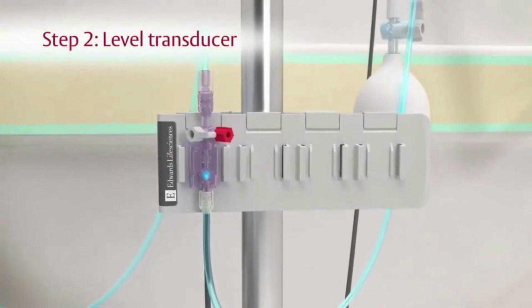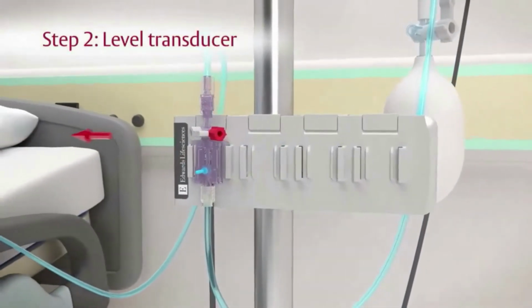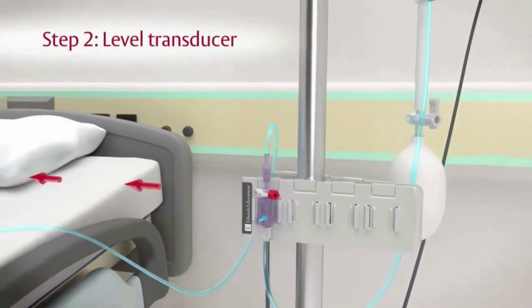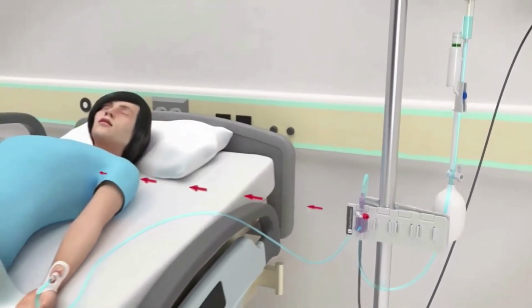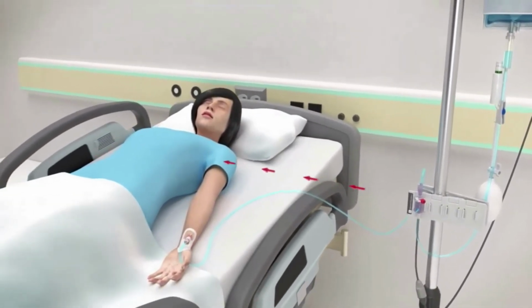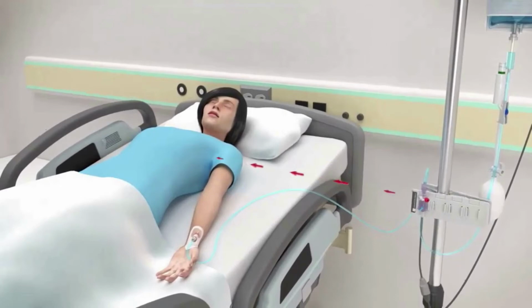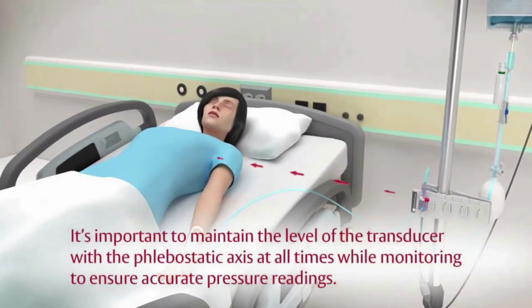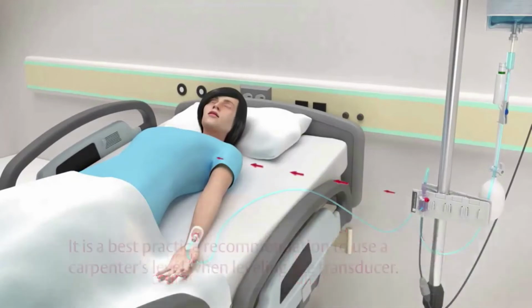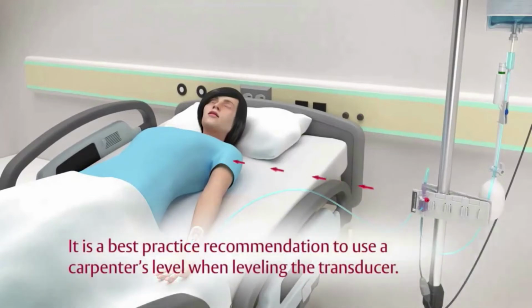Step 2. For intravascular pressure monitoring, level the transducer to the patient's phlebostatic axis, which can be found at the midpoint between the anterior and posterior chest wall at the 4th intercostal space. Note, it's important to maintain the level of the transducer with the phlebostatic axis at all times while monitoring to ensure accurate pressure readings. It is a best practice recommendation to use a carpenter's level when leveling the transducer.